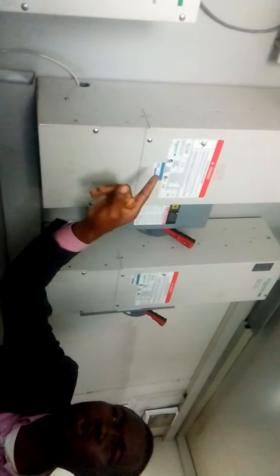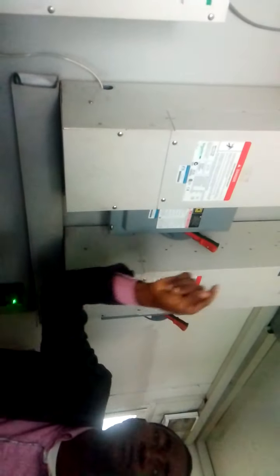This charge controller is designed to work for a 24 volt and 48 volt battery system. This battery system arrangement is 48 volt, so it can charge a 48 volt battery bank arrangement. We have 2 volt batteries, 2000 amp hour at C10, 24 quantity, 24 times 2 all in series, that's 48 volts. So with MPPT you can arrange up to 600 volts, and by the algorithm design, it can sufficiently charge the battery arrangement.